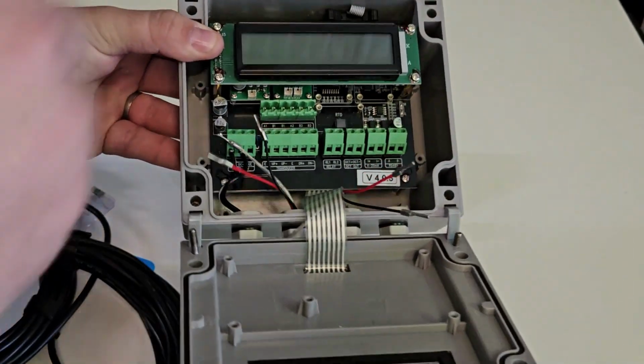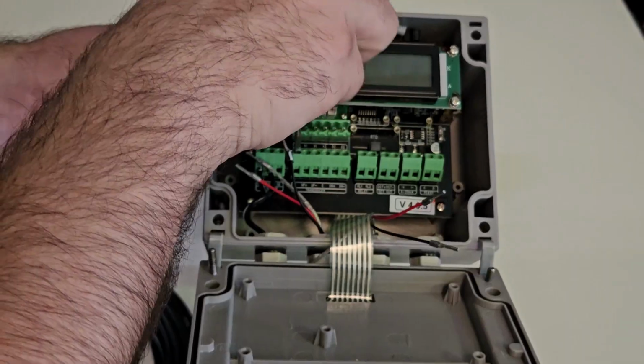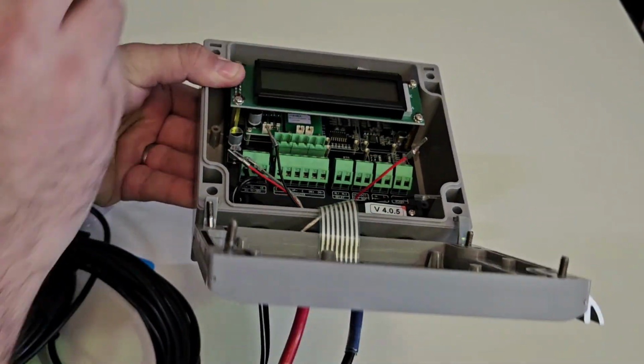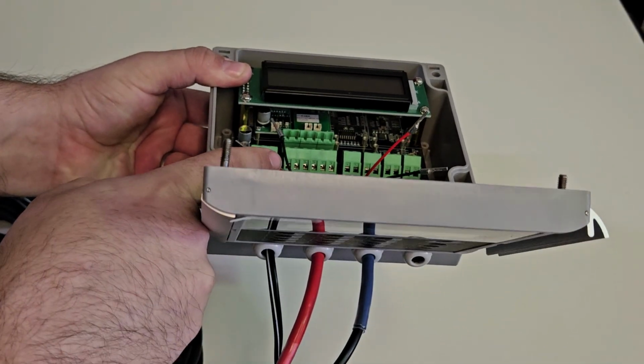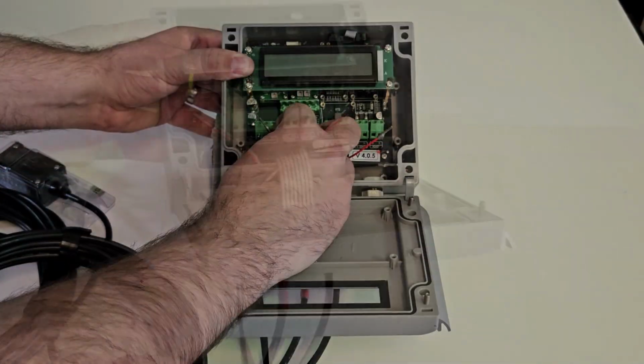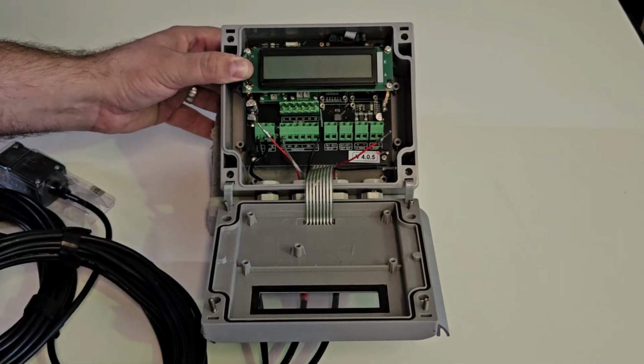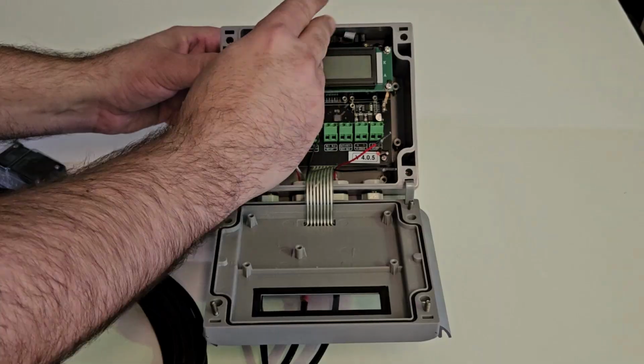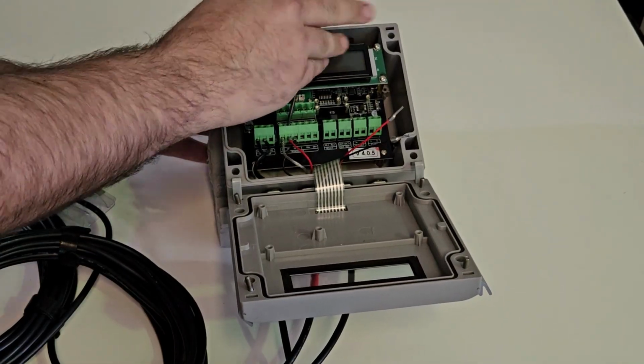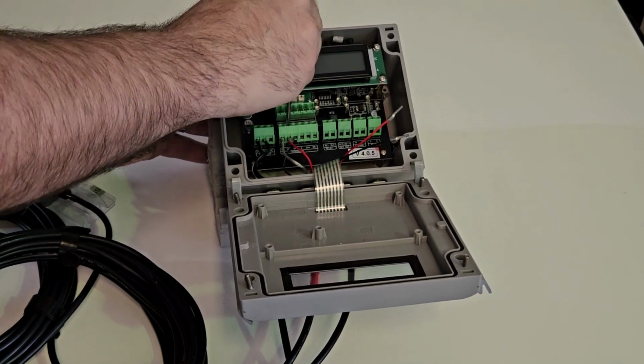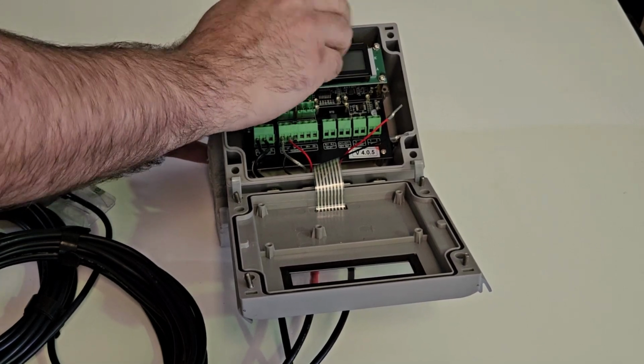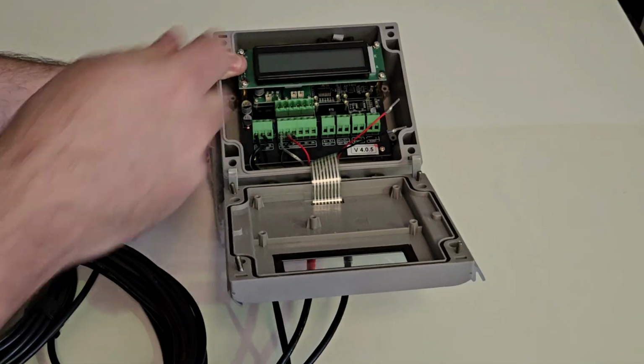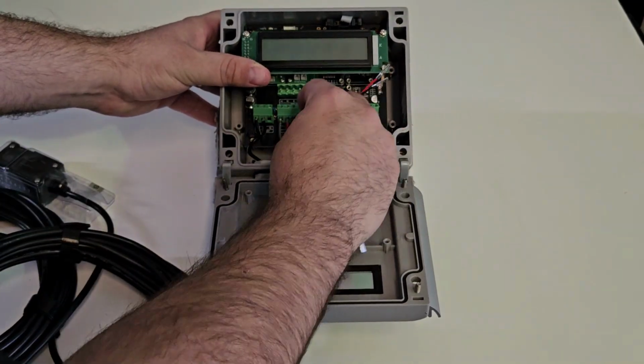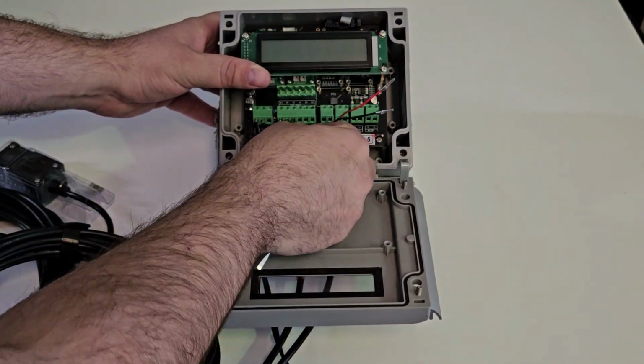Prepare each of these 6 ports for the transducer cables by unscrewing each one. Ensure the ports open enough to install the wires. Insert the wires into each of the ports, noting that the grey wire is for port marked E, red is positive, black is negative. Be sure that the upstream cable is wired to the UP ports and the downstream cable is wired to the DN ports. So we have inserted the wires on the upstream side first, and then inserted the wires to the downstream side.